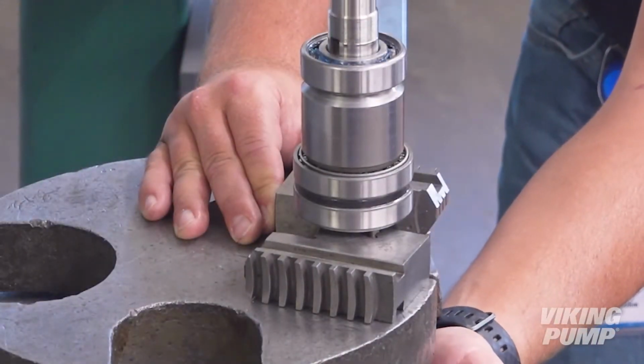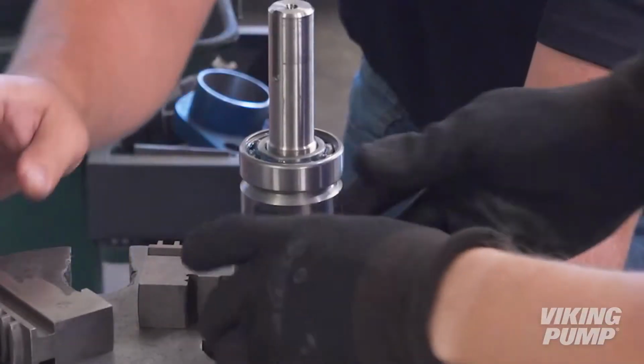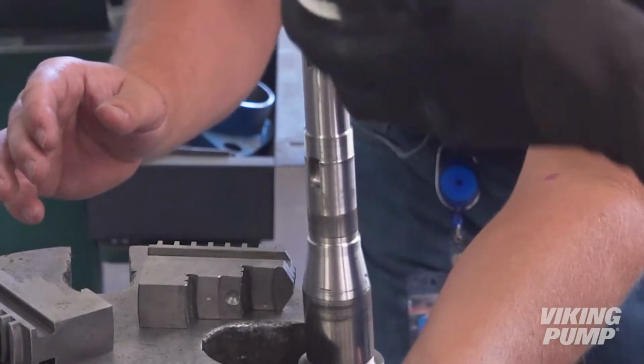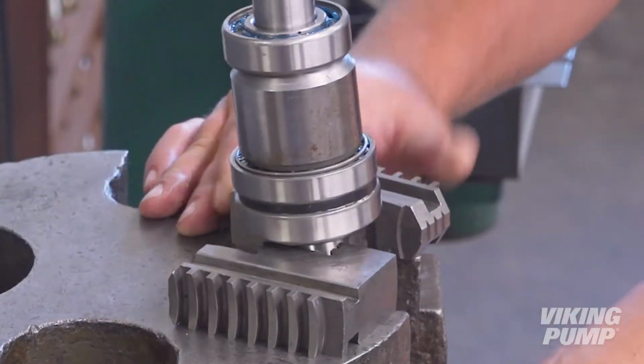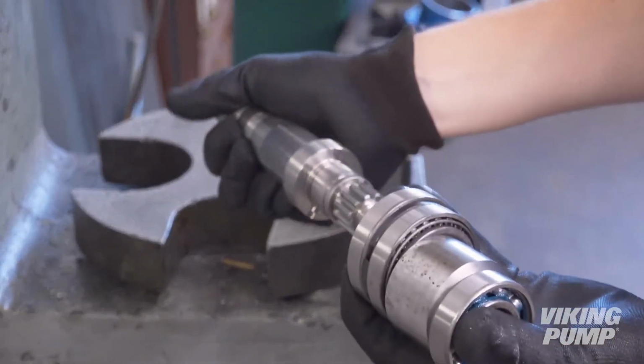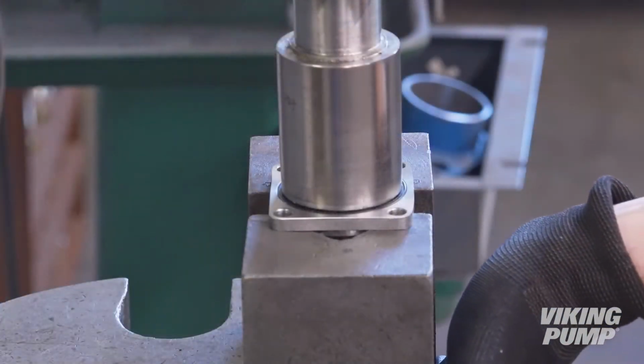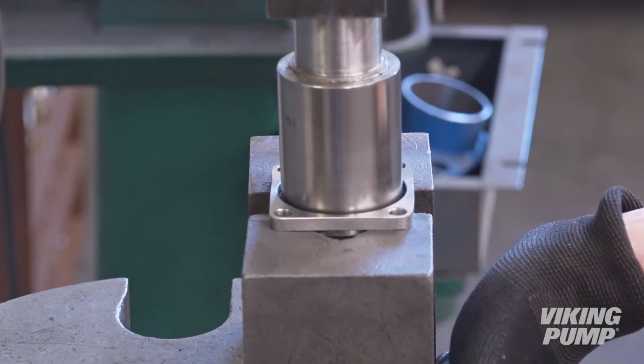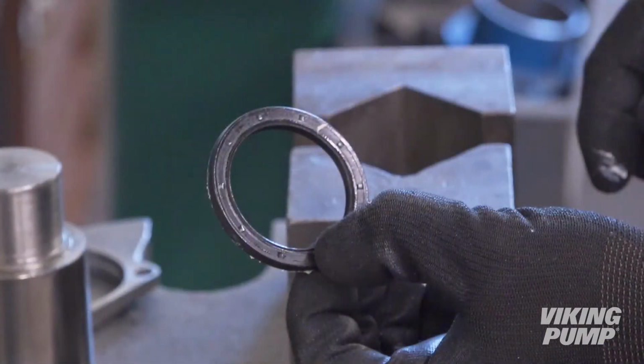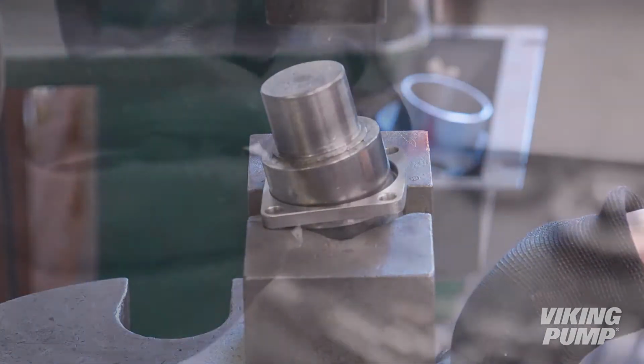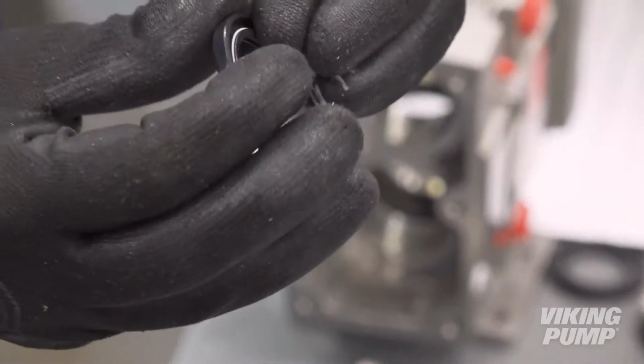Next, using V-blocks for support, press the bearings and spacers off each shaft. Press out and discard the bearing retainer lip seals. It is now time to begin reassembling the pump.